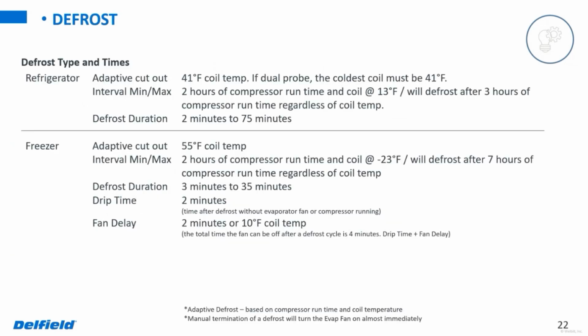So the defrost on these. We covered a little bit of this in that last illustration. The big thing that we want to cover here is the intervals on these. So you'll notice for the refrigerator on top, we're looking for 2 hours of compressor runtime and a 13-degree coil temperature. So we need to have both of those occur for the unit to go into a defrost.